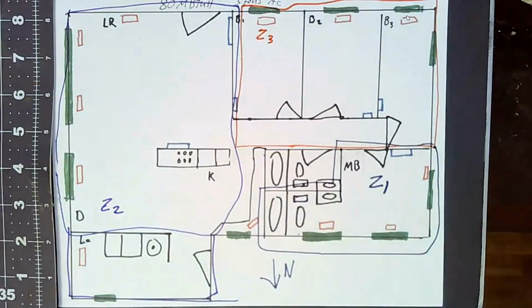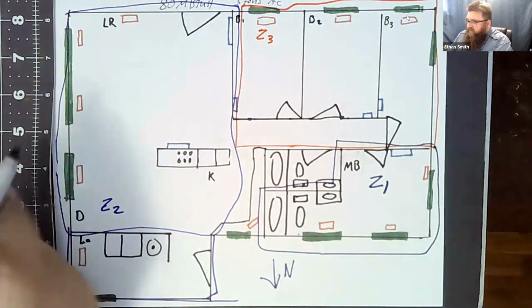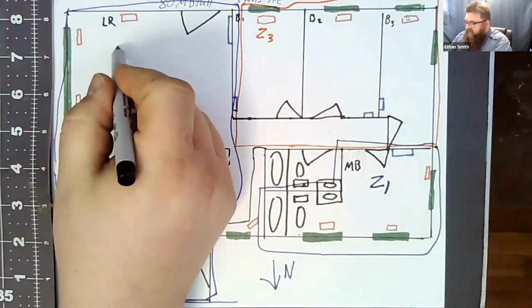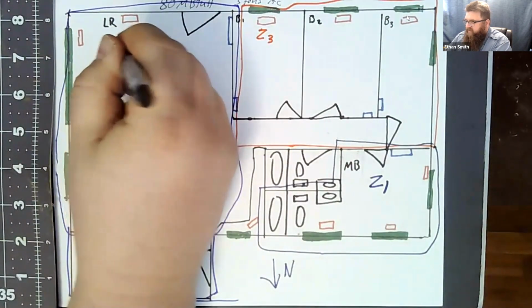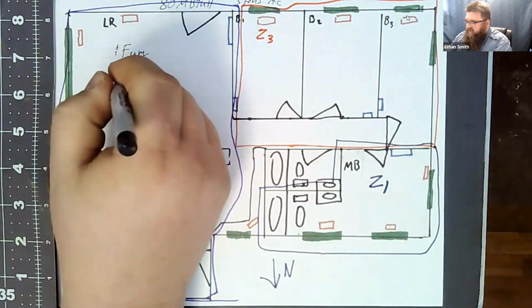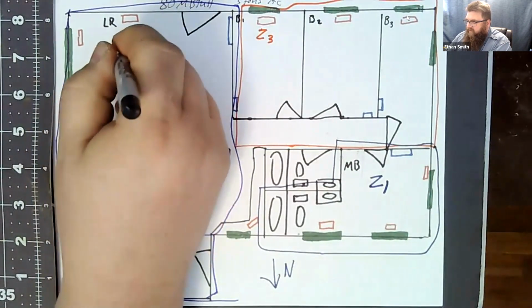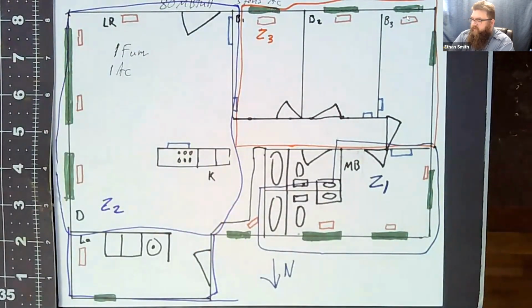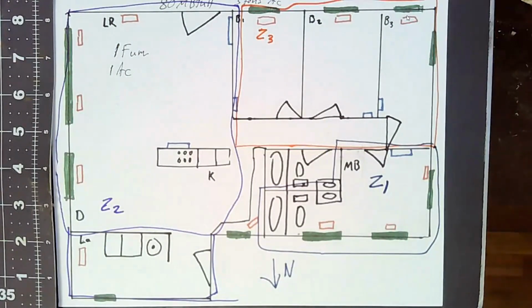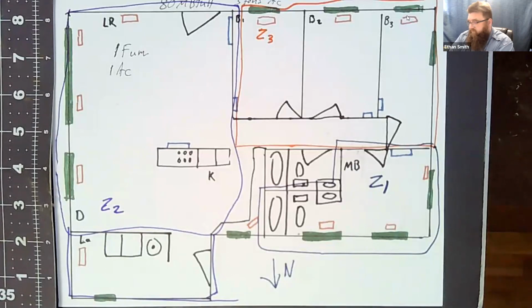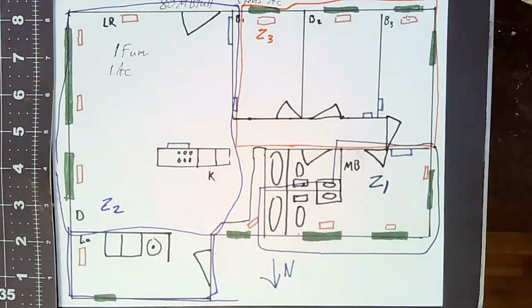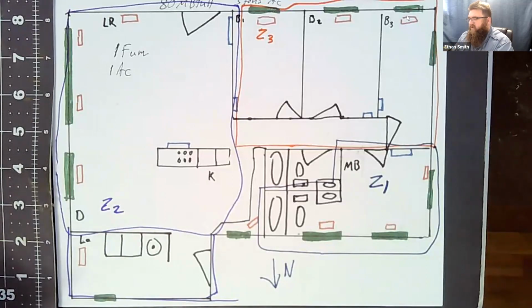Now let's talk about equipment. So my first scenario was a single stage furnace and a single stage AC. Okay, what are my airflow requirements for those? 115%. Again? 1.15. No, that's maximum sizing, maximum CFM.